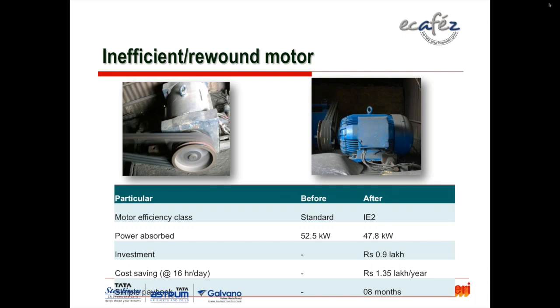The first photograph shows the motor which was there, a standard motor of 52.5 kilowatt rating, and the operating efficiency of this motor was 85%. Although a standard motor of this size should have a design efficiency of 91.7%, what we measured was 85% because it has been rewound at least twice. So we recommended the unit to go for an IE2 motor.